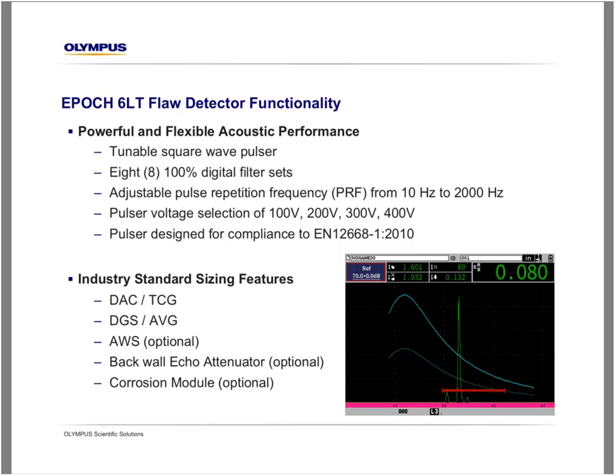It allows inspections both of structural steel when using 2 or 4 megahertz, but also for wind blade inspections when you're dealing with very thick composite materials and attenuating materials. We can very effectively utilize low frequency transducers like a 500 kilohertz or below and still get very strong power output. You'll see a little further down this list, our pulser voltage is also selectable up to 400 volts, which is really class leading in terms of the market segment that we're targeting here with this EPOCH 6LT flaw detector. So again, this flaw detector is much more flexible than what you may be used to in a very portable instrument. We do maintain our very strong signal to noise ratio functionality through our digital filtering.